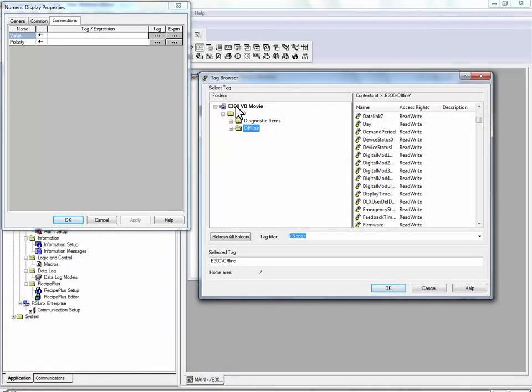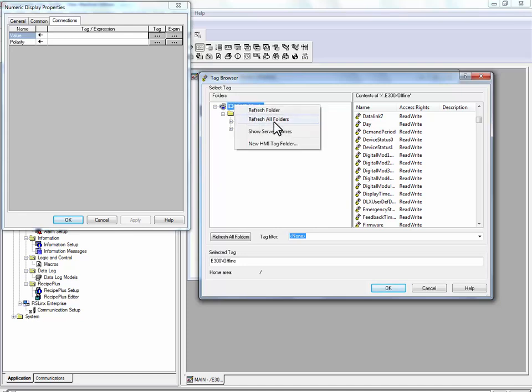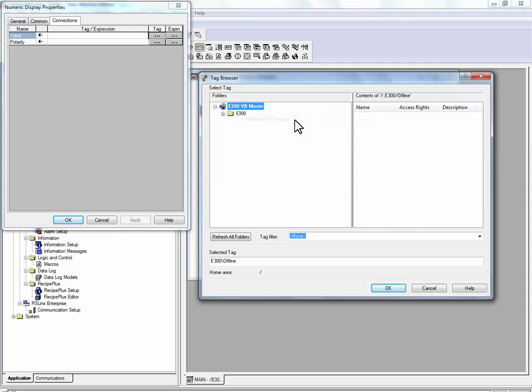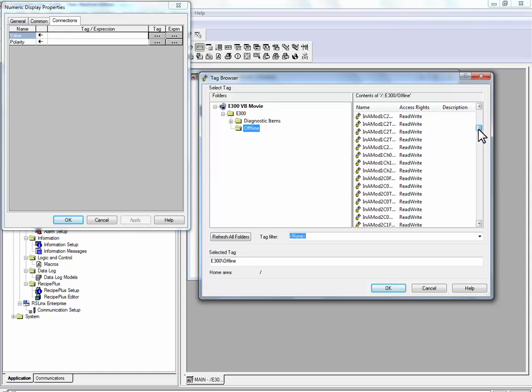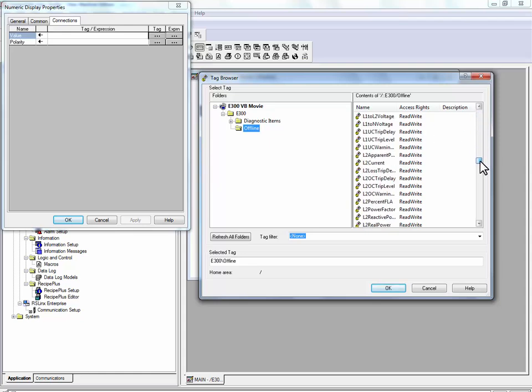To make sure you have the latest device shortcuts, right click on the project and press refresh all folders. The tags that we can choose from are located under the E300 shortcut and the offline folder. For L1 current, we will select the L1 current parameter.